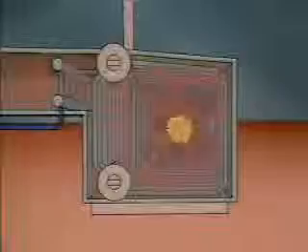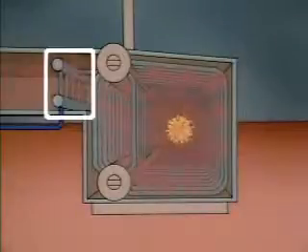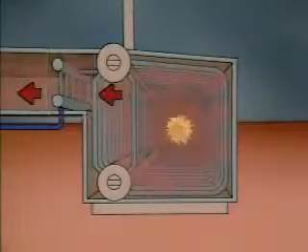One way boilers are made more efficient is by heating the feed water before it enters the boiler. If the feed water is preheated, the boiler will require less fuel to produce steam. A device used to preheat feed water is called an economizer. Economizers are often used in water tube boilers; an economizer is basically a series of water tubes located in the flow path of the combustion gases.